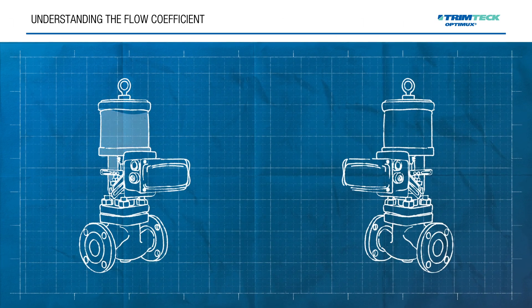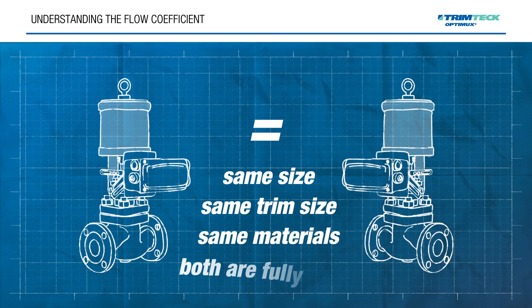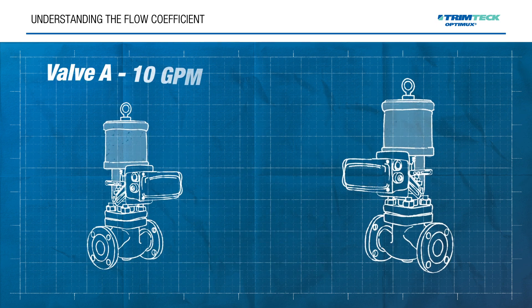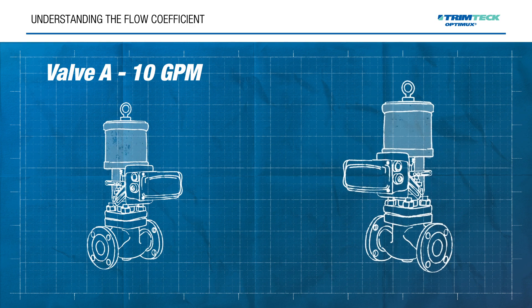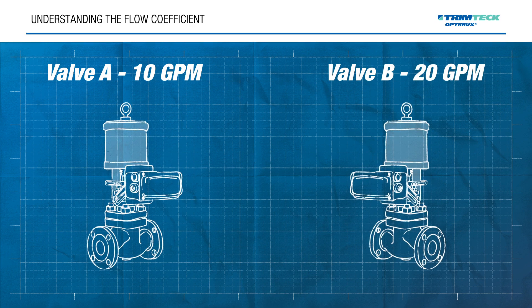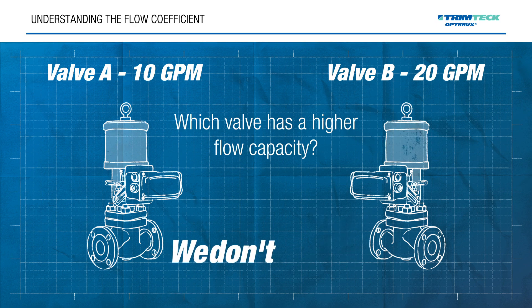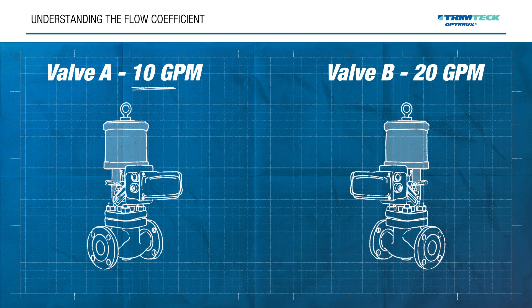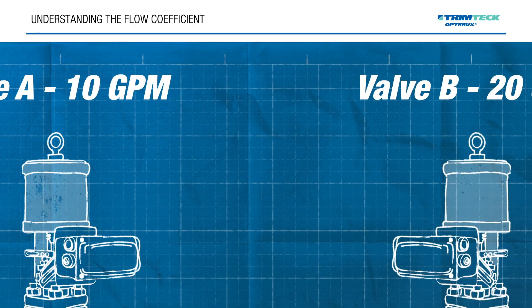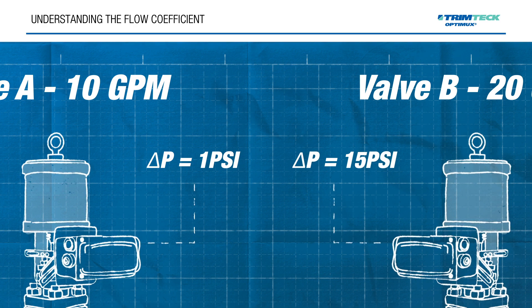To illustrate this, let's look at two identical valves — same size, same trim size, same materials of construction. Both are fully open and we observe the following: Valve A has a flow rate of 10 gallons per minute and Valve B is flowing 20 gallons per minute. If you ask which valve has a higher flow capacity, typically folks will say Valve B because it's flowing 20 gallons per minute. But the real answer is that we don't know. We take a closer look and find that Valve A has a 1 psi pressure drop across it and Valve B has a 15 psi pressure drop across it.